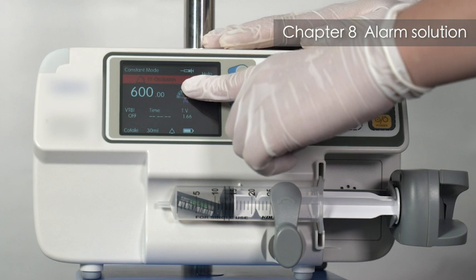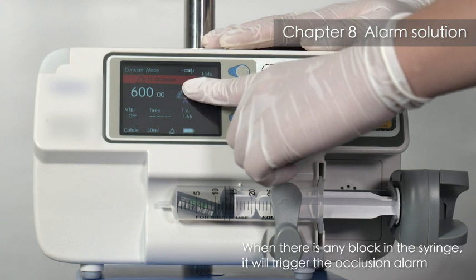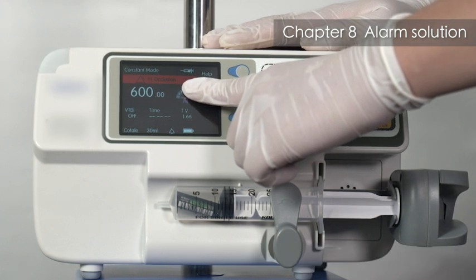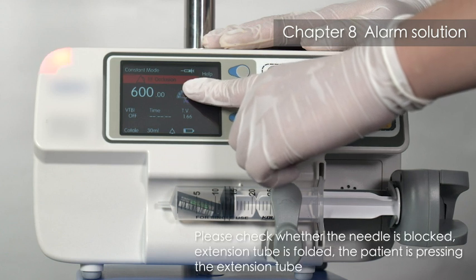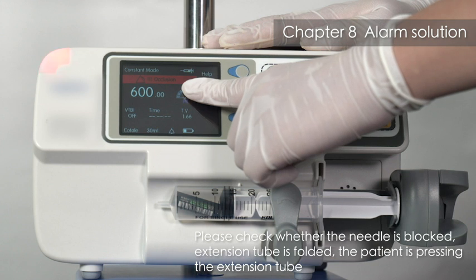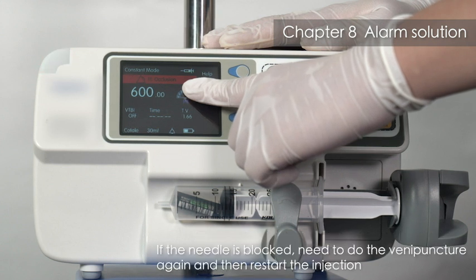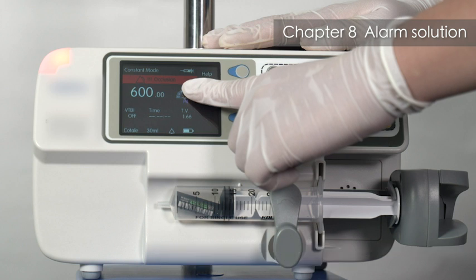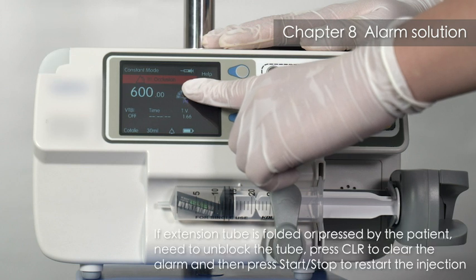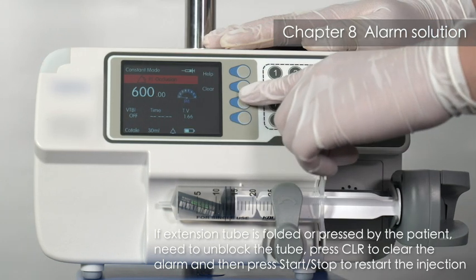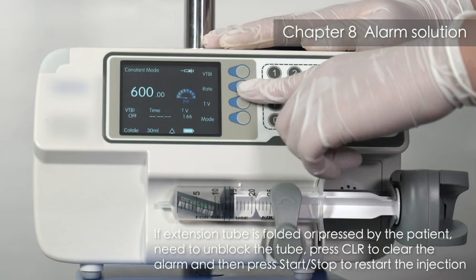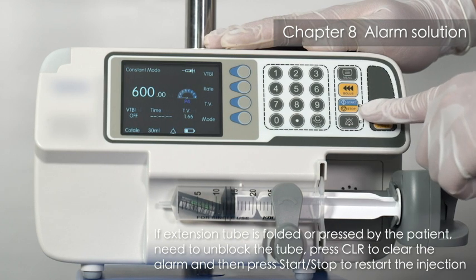Occlusion alarm. When there is any block in the syringe, it will trigger the occlusion alarm. Please check whether the needle is blocked, the extension tube is folded, or the patient is pressing the extension tube. If the needle is blocked, need to do the venipuncture again and then restart the injection. If extension tube is folded or pressed by the patient, need to unblock the tube, press CLR to clear the alarm, and then press Start/Stop to restart the injection.